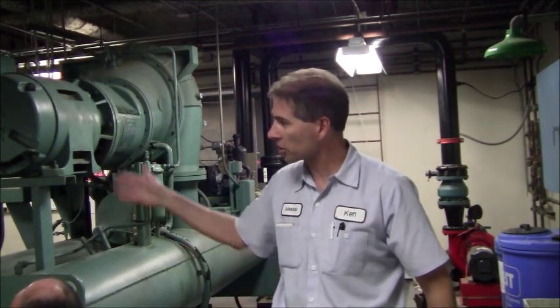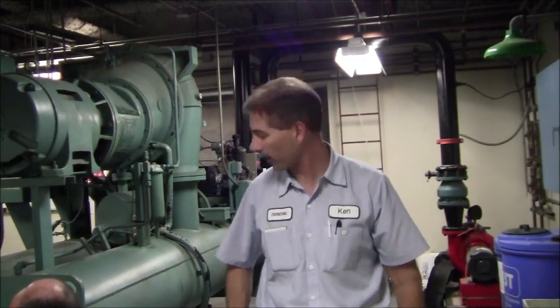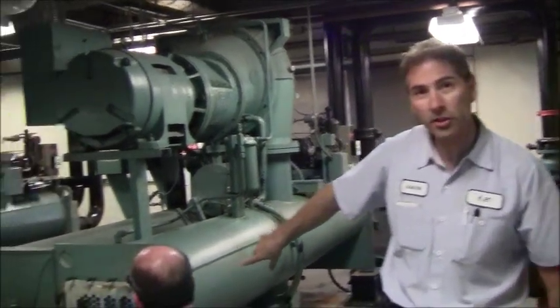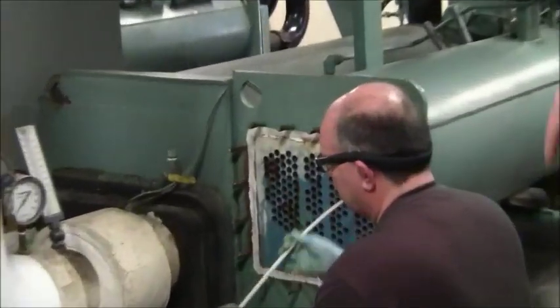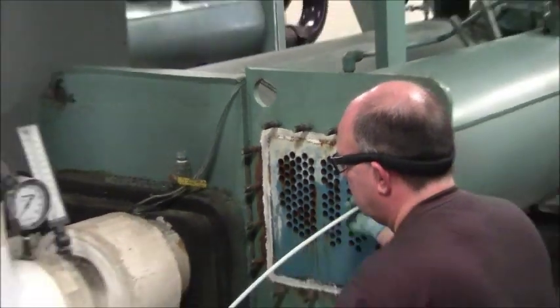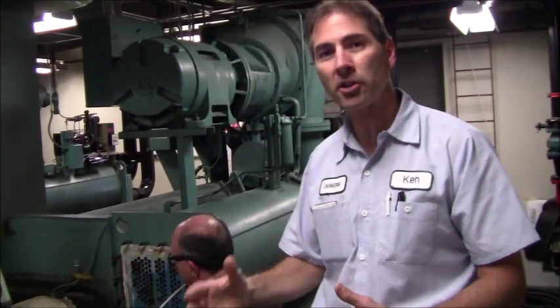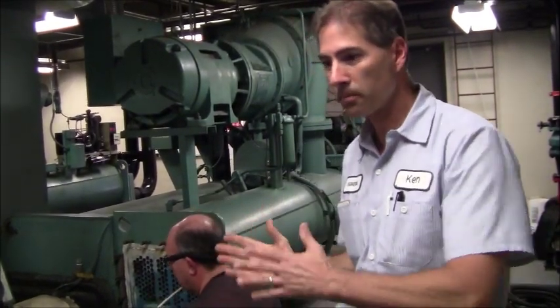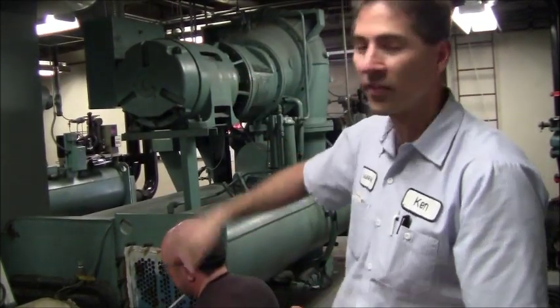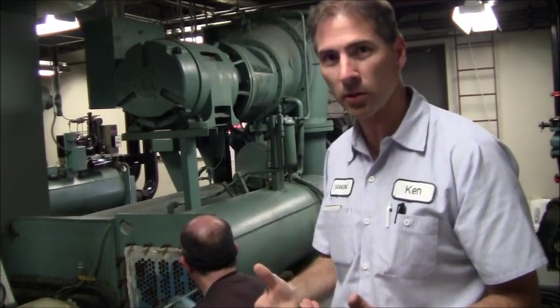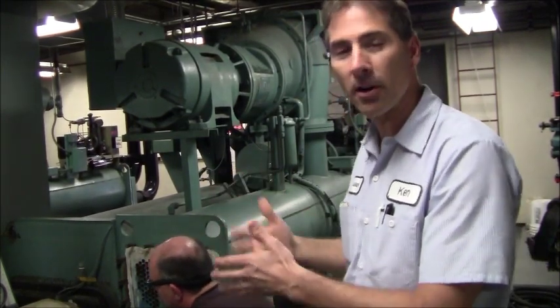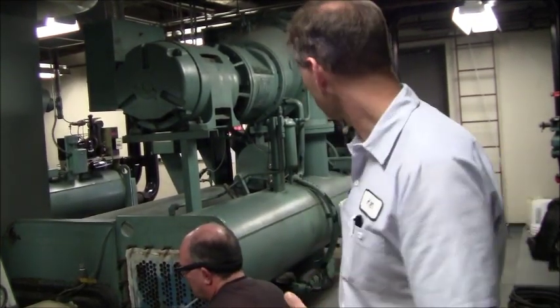We have, not on this chiller, but the chiller next to it, a tube sheet repair where you see that blue coating on this condensing tube sheet. Well, we've got some pitting going on in the chiller next to it, so we have to have an epoxy coating put on there, which is going to bring that back out to a natural thickness, extending the life of that tube sheet, therefore extending the life of that chiller. So these are some things that we do, part of the repairs and maintenance, to extend out the life expectancy of the chillers.